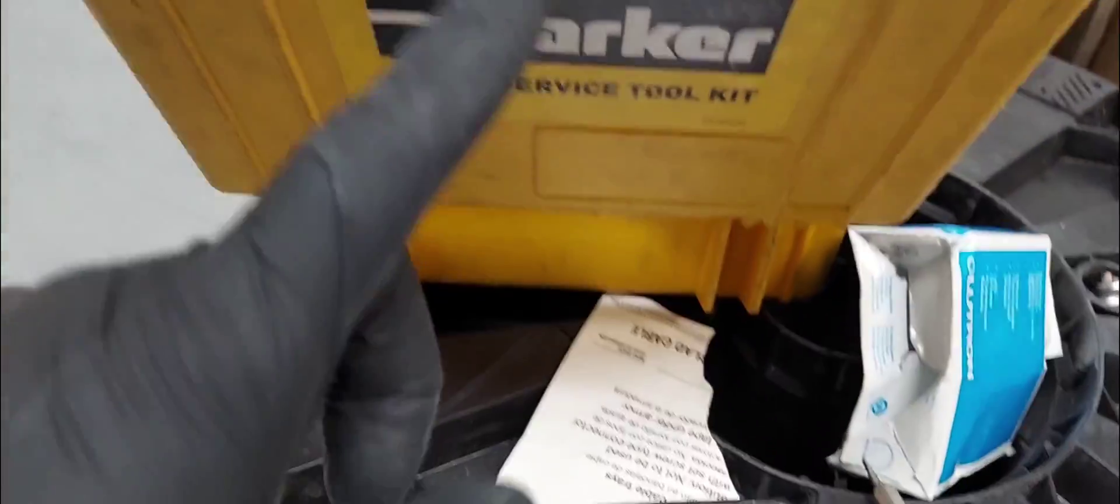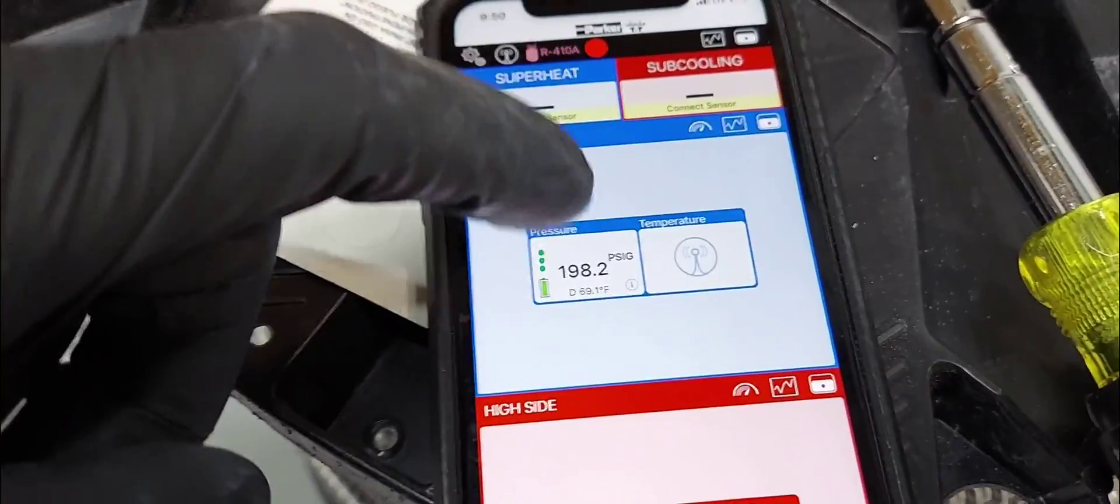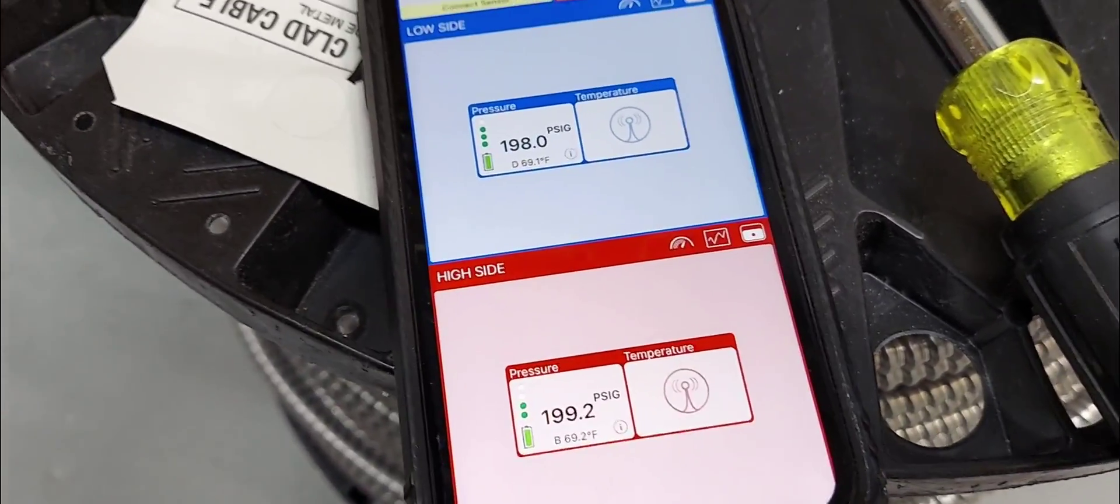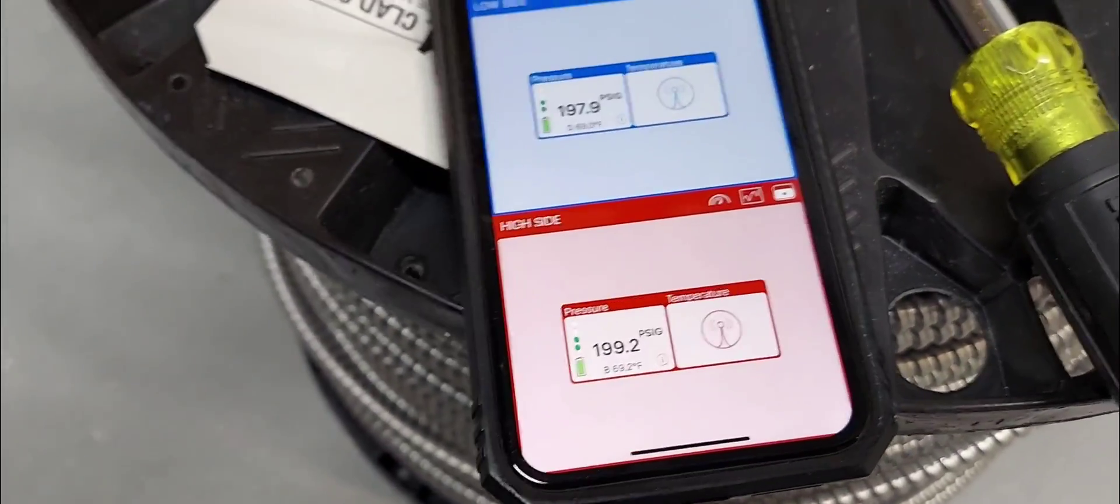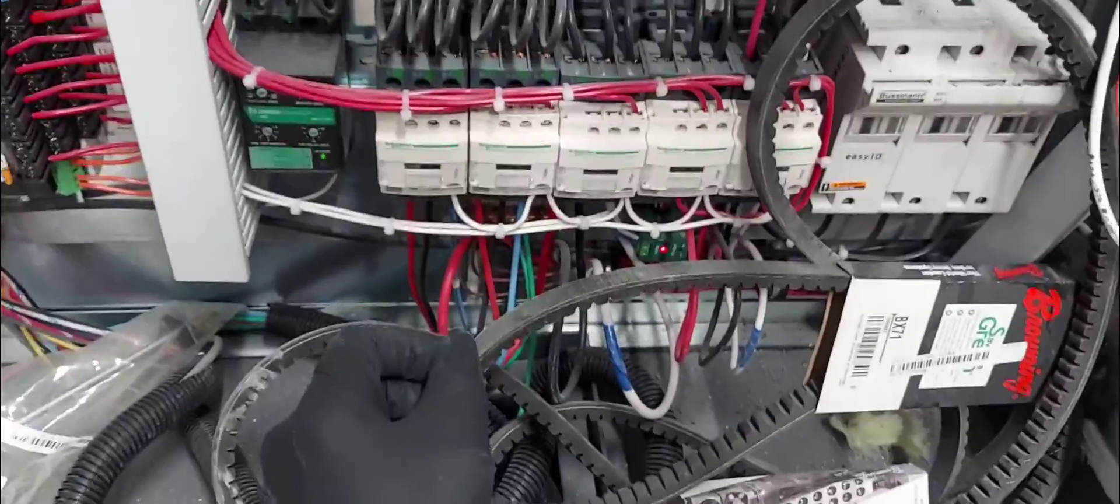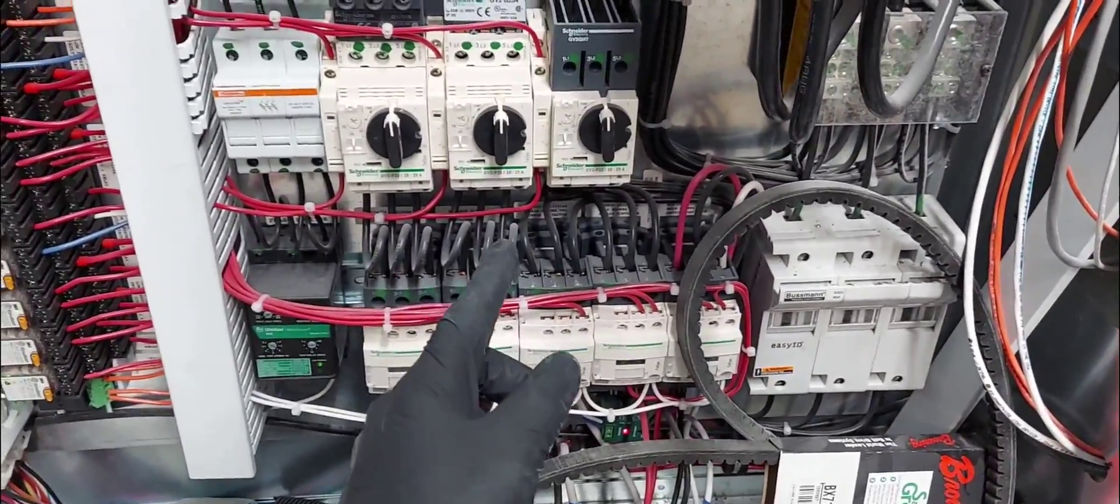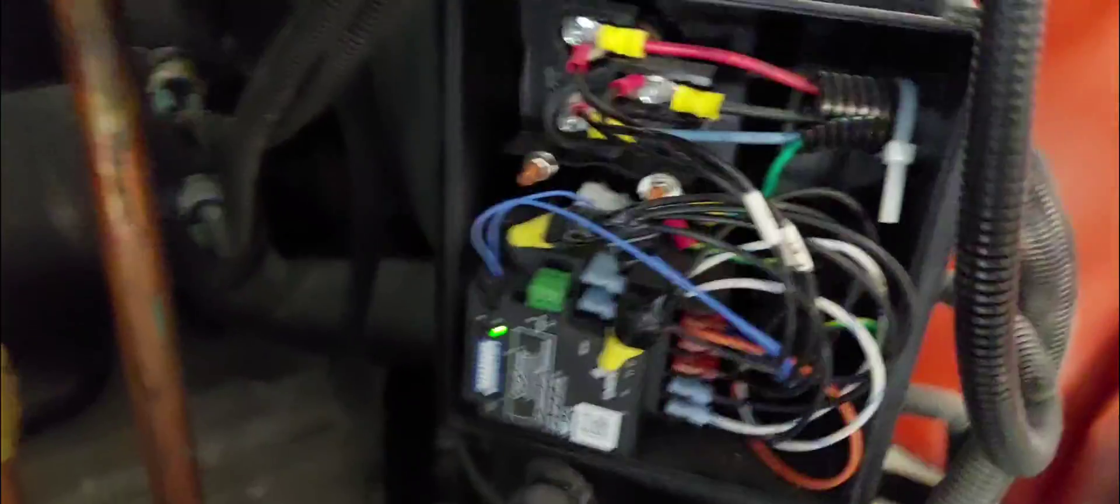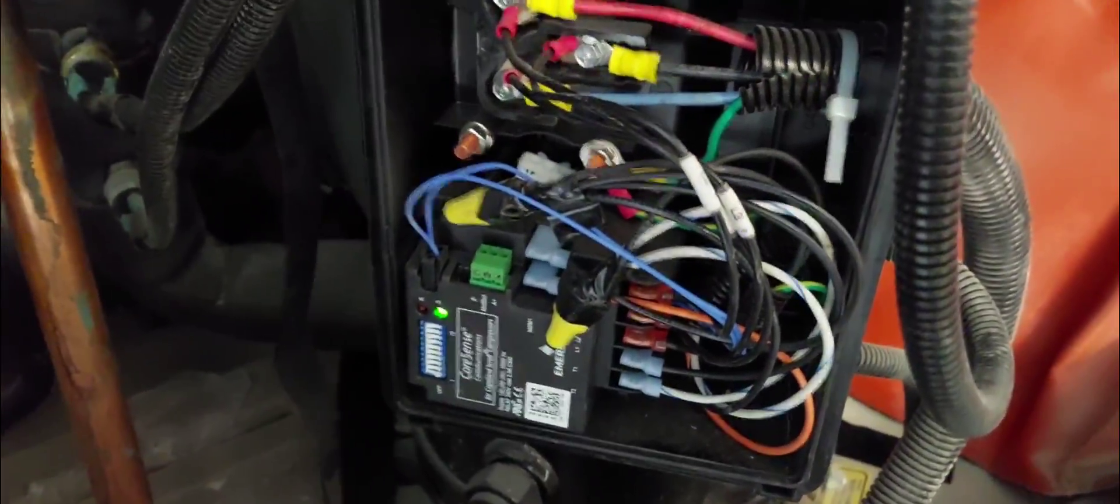Literally before the compressor even starts, I didn't even hear the compressor start. I have my Parker Smart Probe hooked up. The pressures, standing pressures, are looking rather high. It's R-410A but it just didn't start. I just don't know why. I gotta figure that out guys. I think this is the second compressor - it just started, just clicked in. I had to start her off but it worked - no more fault.